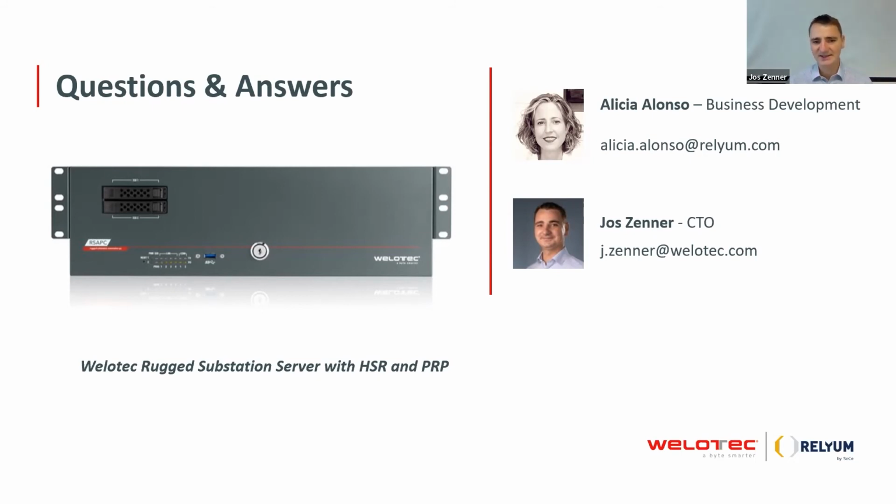So for the virtual machines, it's like with a standard Ethernet interface. So multiple virtual machines can use the same Ethernet interface and connect to the PRP network. The idea behind is that to the outside, the PRP card has two ports to connect to LAN A and LAN B, and to the inside, it is just one standard Ethernet port. So all the processing and acceptance and discarding of the frames is happening within the card.